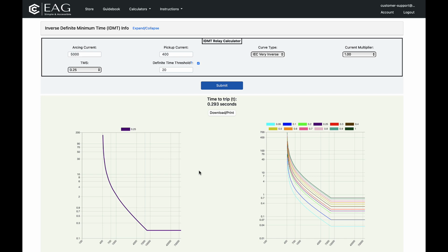We must also factor in the time for operation of the switchgear. This again can be obtained from manufacturer's data, commissioning, or preferably from timing tests, but as a guide for the purposes of arc flash calculation, a generic allowance can be built in. A table of allowances and generic switchgear operating times are given in Chapter 8, Data Collection.